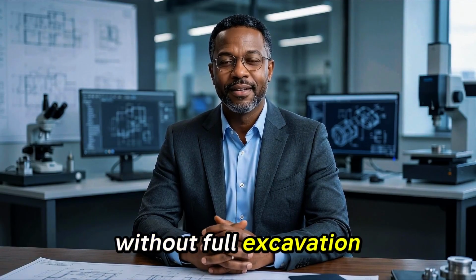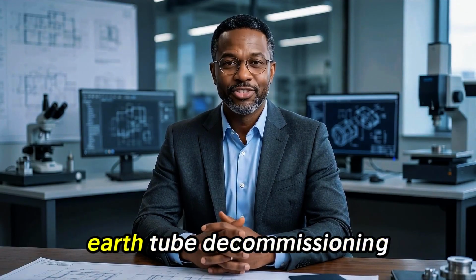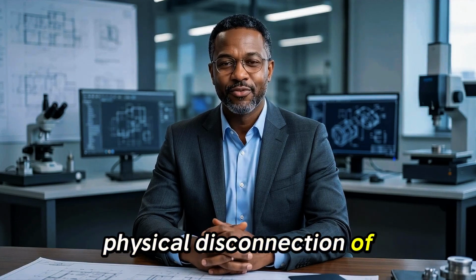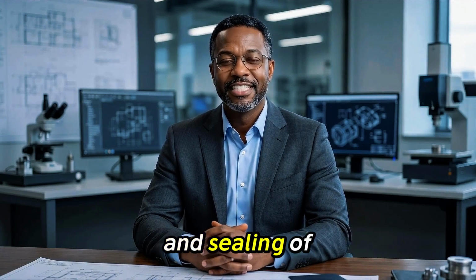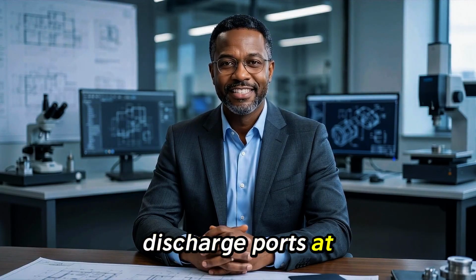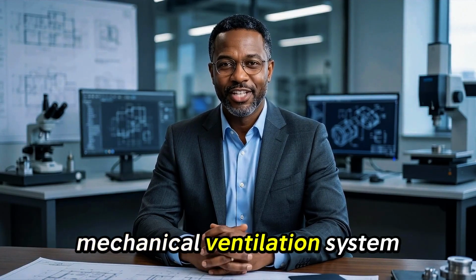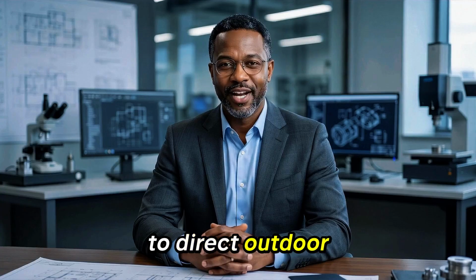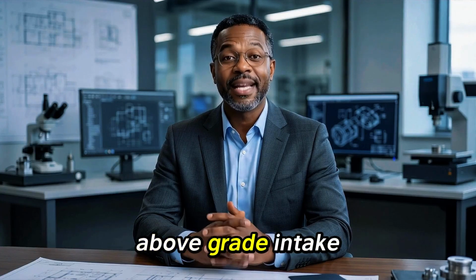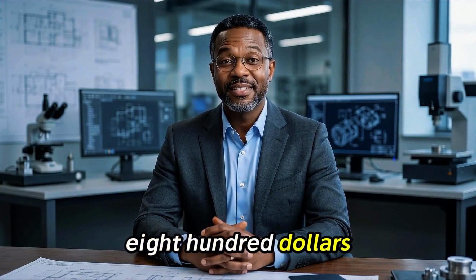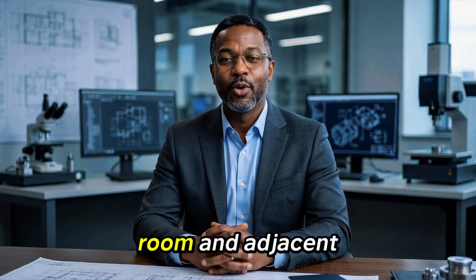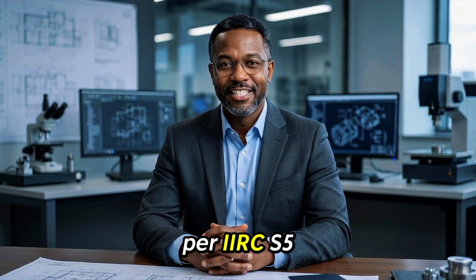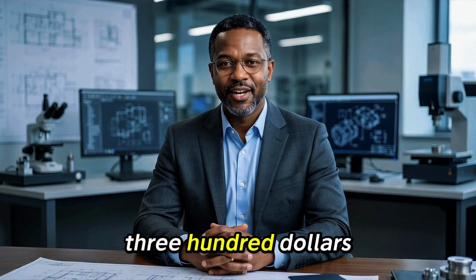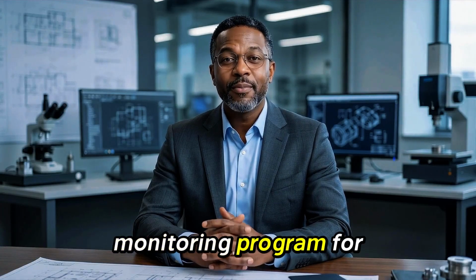Remediation required complete earth tube decommissioning, physical disconnection of all 4 pipes from the ventilation system, and sealing of the intake and discharge ports at $6,200, mechanical ventilation system reconfiguration to direct outdoor air intake from a properly located above-grade intake point at $4,800, indoor mold remediation of the mechanical room and adjacent ductwork per IICRC S520 at $7,300, and a medical monitoring program for the family.